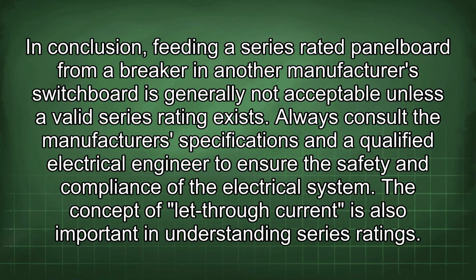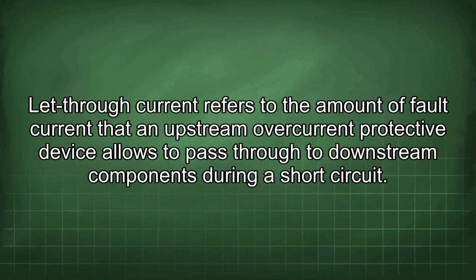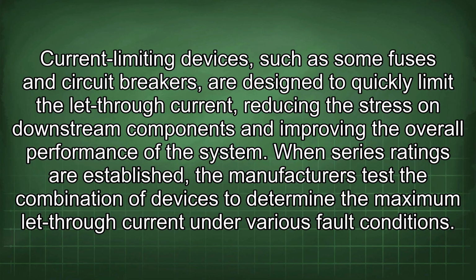The concept of let-through current is also important in understanding series ratings. Let-through current refers to the amount of fault current that an upstream overcurrent protective device allows to pass through to downstream components during a short circuit. Current-limiting devices, such as some fuses and circuit breakers, are designed to quickly limit the let-through current, reducing the stress on downstream components and improving the overall performance of the system. When series ratings are established, the manufacturers test the combination of devices to determine the maximum let-through current under various fault conditions.